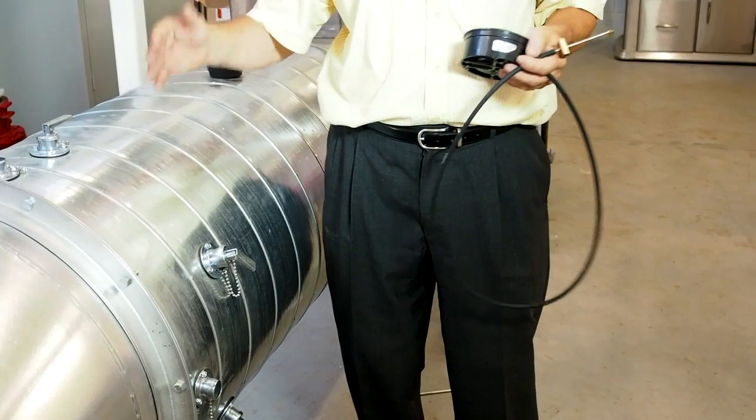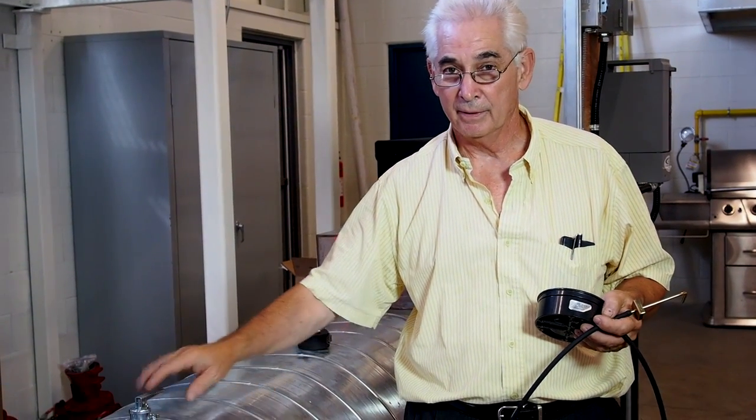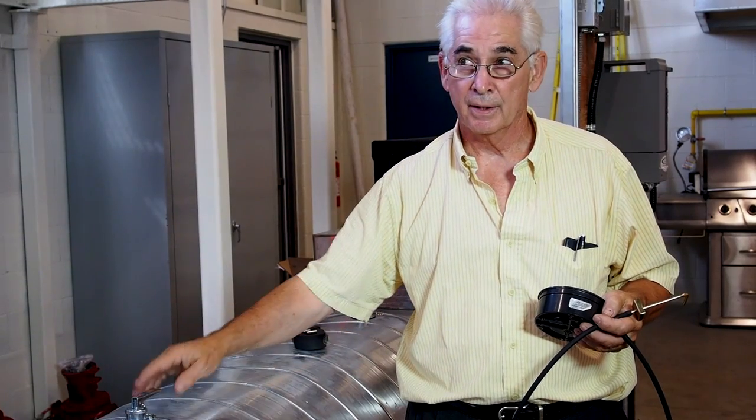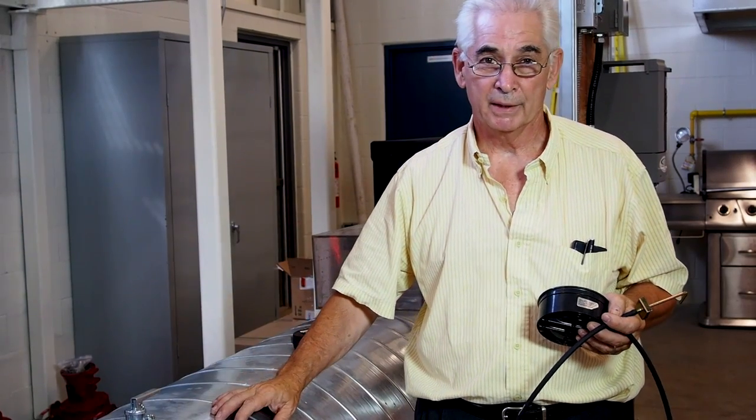Again, we're trying to determine what's the average velocity through the duct. We know the area of the duct is 3.14 square feet. If we measure the velocity here at 1,000 feet a minute, then we determine that right here, the flow rate is 3,142 cubic feet per minute.